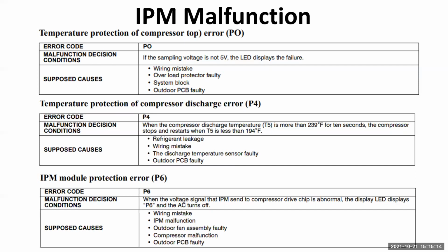You want to check your compressor. Make sure the compressor ohms out correctly. Unplug the compressor. Does the code go away or does it change? Is your compressor noisy? You want to check and make sure your compressor didn't get hot. Melted the stickers, burned them a little bit, maybe curled them, discolored them. You can check the interior of the compressor blanket, see if it's discolored. That's not always 100% accurate because sometimes just age discolors them too.